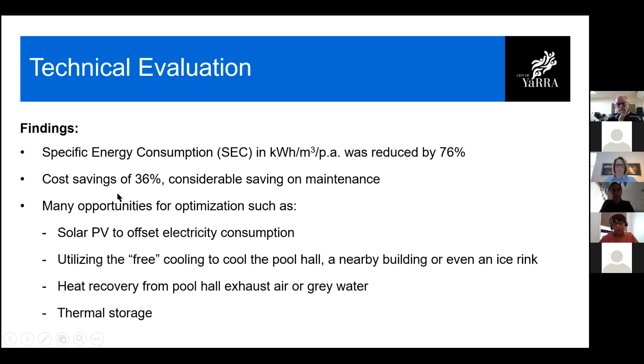We also realized how many opportunities for optimization there are with such a system compared to a conventional gas system. The more solar we can fit on the roof, the better the efficiency outcomes, because it will all be absorbed on site. We can utilize free cooling, use heat recovery from the pool hall exhaust air or even gray water from our waste lines, and use thermal storage for demand control or load shifting at night. The opportunities are endless for optimization with such a system.